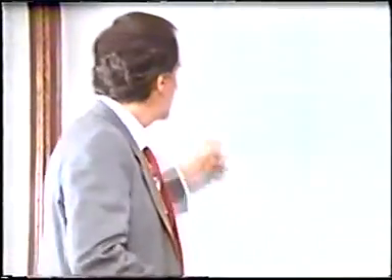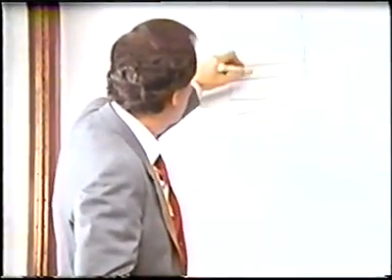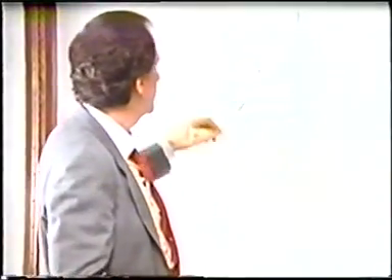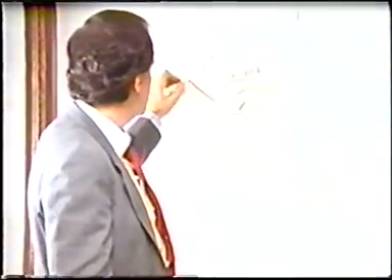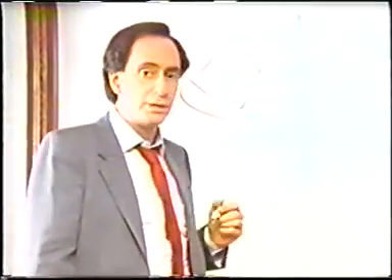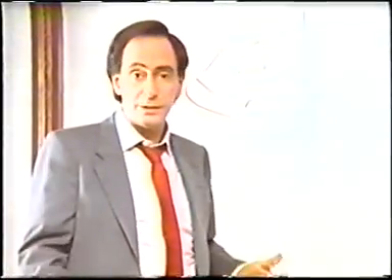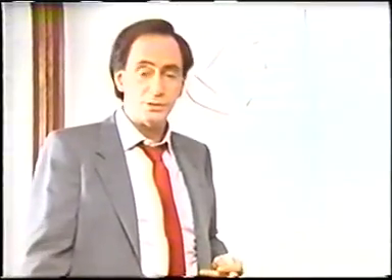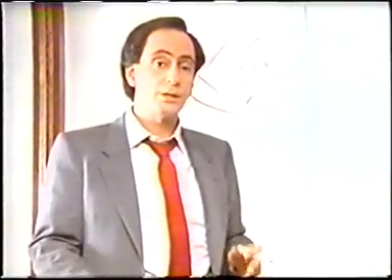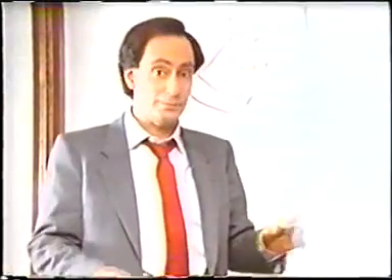These response plans differ. One method is for the fire floor, the 2 floors above the fire, and 2 floors below the fire, to enter the stairwell and descend, re-entering onto a floor at least 3 floors away from the fire. Now, this is a temporary point of safety, where they wait for the all-clear signal or further instructions to evacuate. In non-sprinklered buildings, the initial response is almost always down and out.